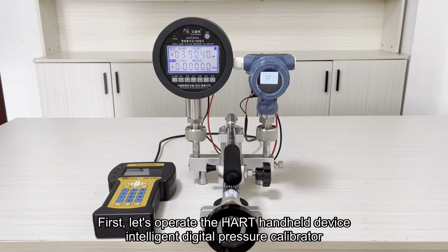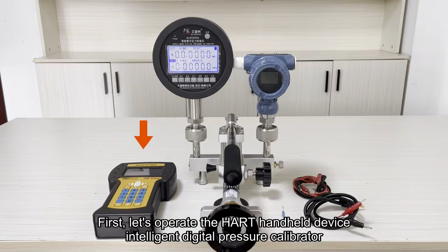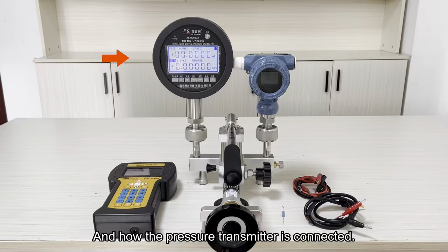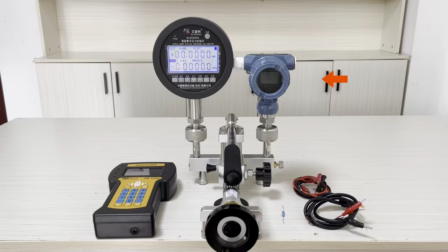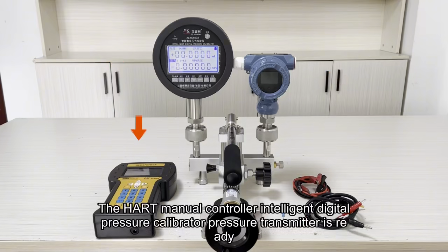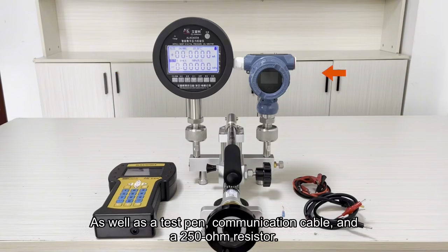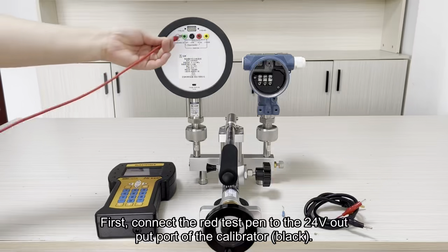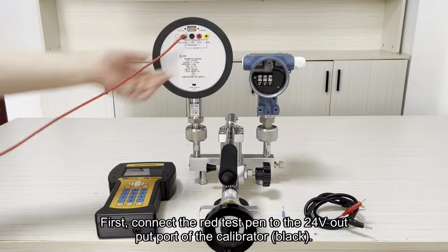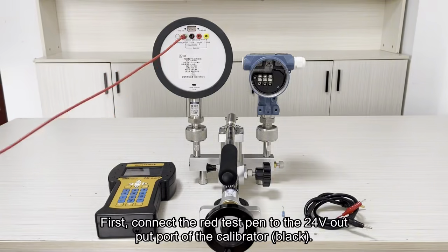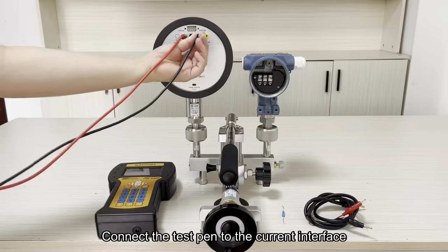First, let's operate the HART handheld device intelligent digital pressure calibrator, and how the pressure transmitter is connected. The HART manual controller, intelligent digital pressure calibrator, pressure transmitter are ready, as well as a test pen, communication cable, and a 250 ohm resistor. First, connect the red test pen to the 24V output port of the calibrator. Connect the black test pen to the current interface.